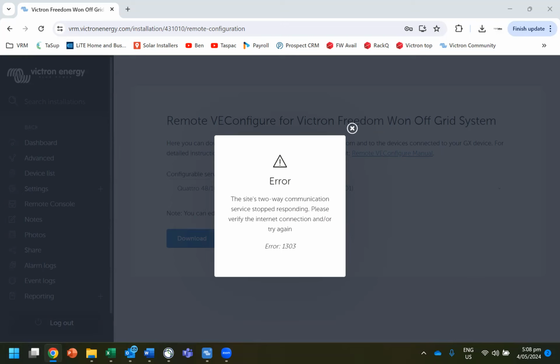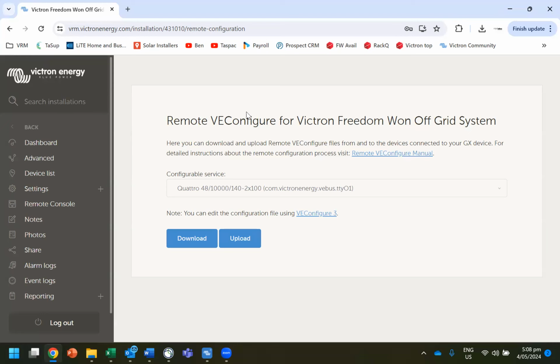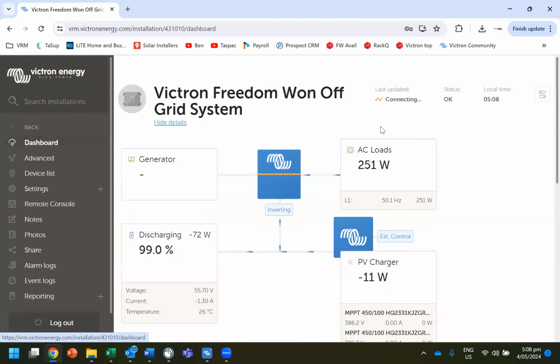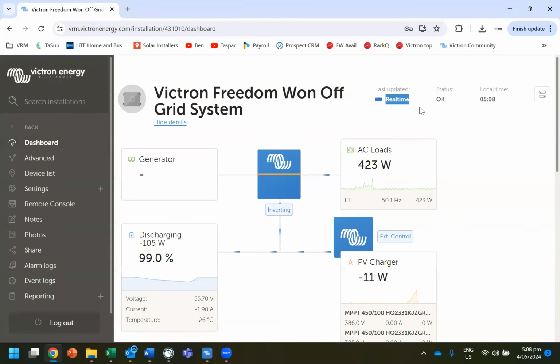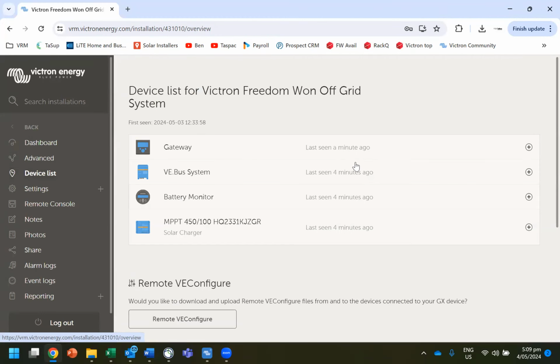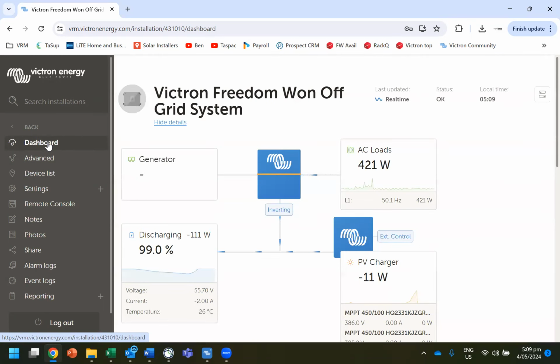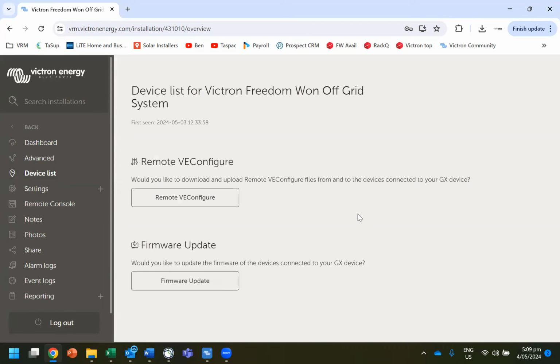Okay, so what we have here is the warning I was talking about, the two-way communication services stop responding. Basically, it's the internet connection because the inverter is shut down and has probably rebooted well and truly by now, but the internet is taking a while on that site. So you can just close that part of the window, go back to dashboard, and we just want to wait until we get to real time, which looks like we're in real time. And then we can go to device list. And it will tell you when it was last seen. And we can also go back to device list and click on the remote VEConfigure.